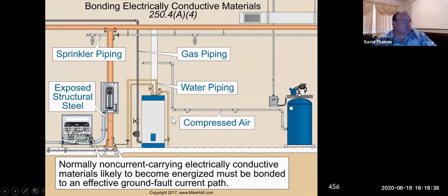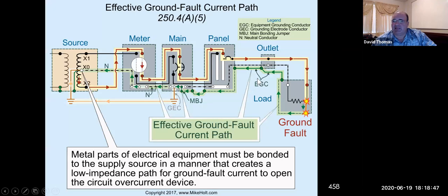Questions? Nobody? Okay. And the other one's effective ground fault current path. We talked about that. It was making sure you have an effective ground path that's a low impedance. So this is actually a really important point. Metal parts of electrical equipment must be bonded to the supply source in a manner that creates a low impedance path for ground fault current to open the overcurrent device.